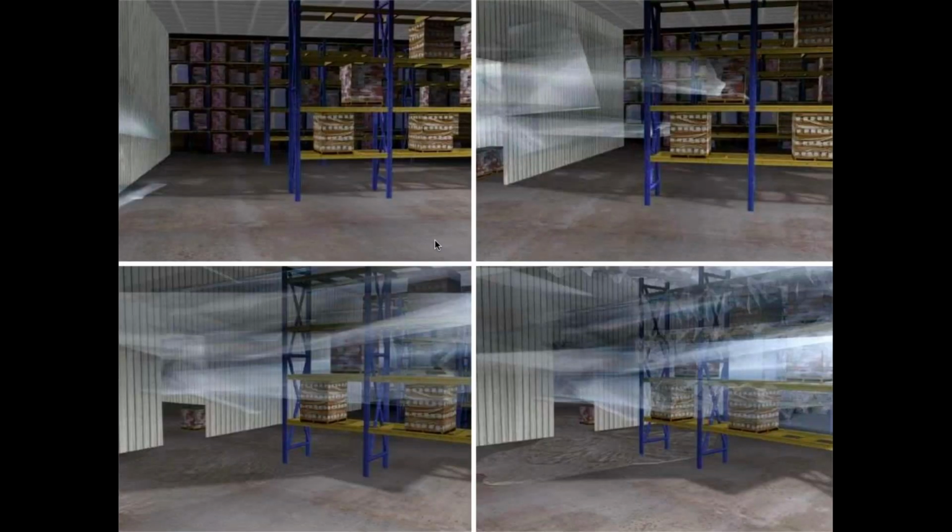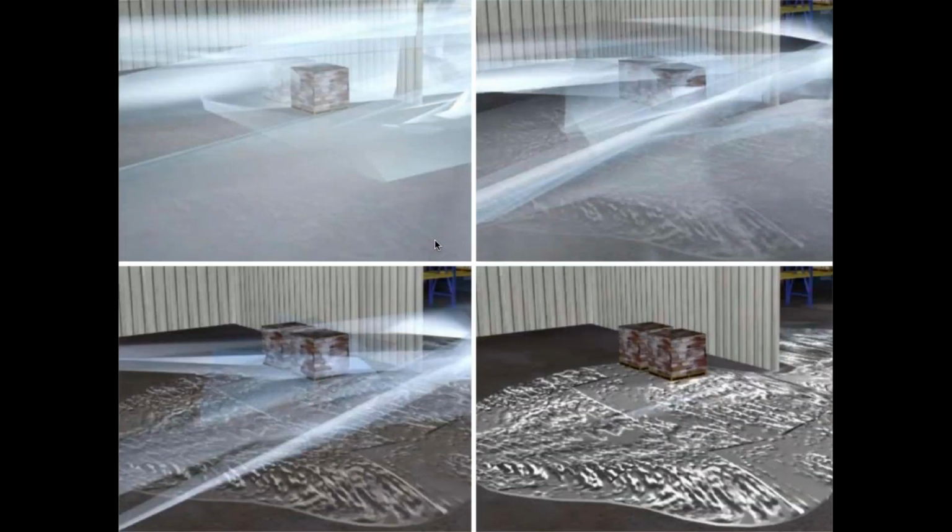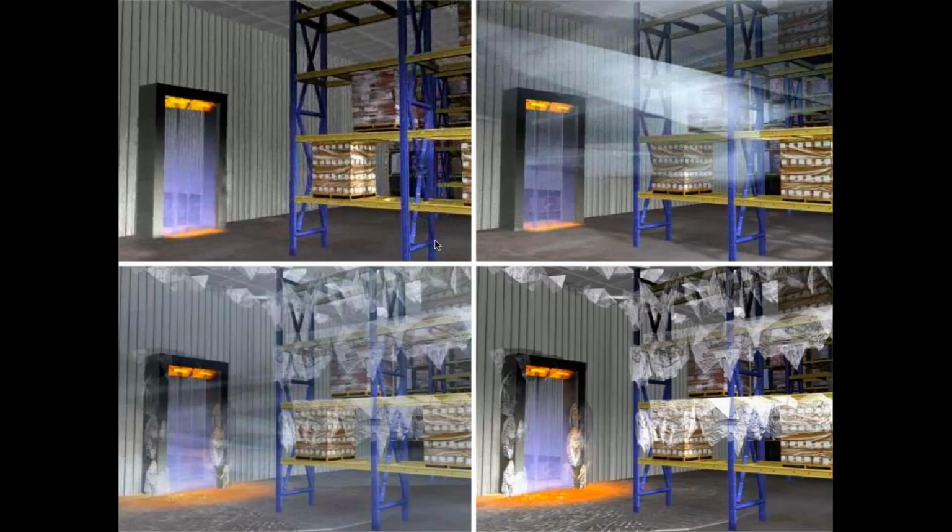This is the fog formation in the cold rooms. This is ice from the roof. If you look at the roof, there is a hell of a lot of condensation, or at -20 degrees, there is all ice formation. So this should be avoided. So when you find that much more ice than expected is getting accumulated, the best way is to do an insulation leak test to find where the moisture is leaking in.